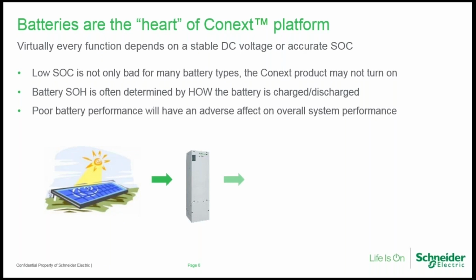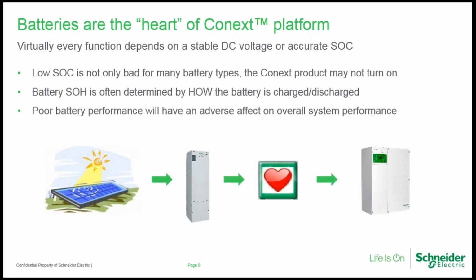Batteries are central to our battery-based system. Without a battery, the inverter and the charge controllers won't even turn on. The question's often been asked in the past, well, can I just get the XW now and add a battery bank later? And the answer is no, not if you want it to power on. It requires minimum DC voltage across the terminals to activate the internal circuitry.